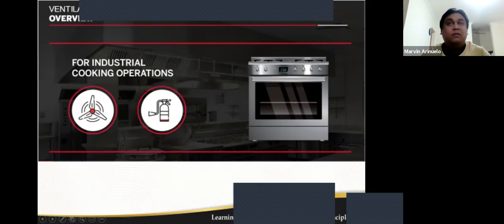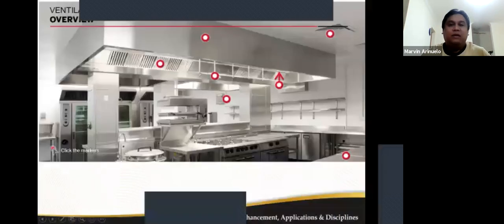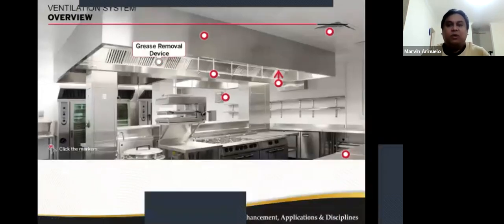And again, it's about the potential fire in commercial cooking establishments because it's a very serious concern. Many commercial cooking operations are part of, as we discussed earlier, healthcare or any other occupancy, which could have a significant risk to life safety. For industrial cooking operation, the ventilation and fire control must be considered a major building system with several components. Okay? And again, as we discussed earlier, those components must be addressed properly for the fire system to become effective.